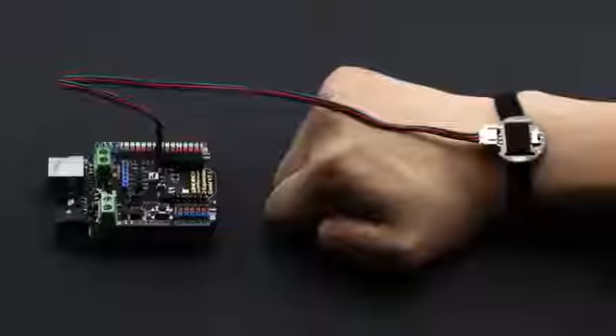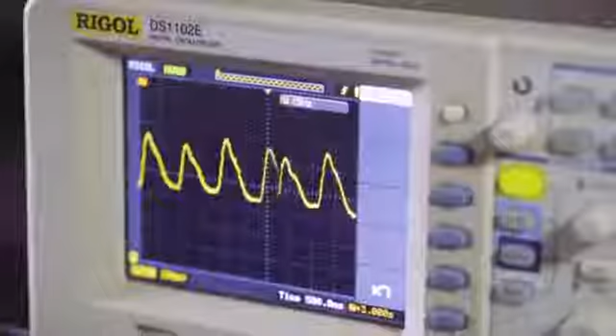Before moving into setup, let's first take a look at the optical heart rate sensor and how it works. The optical heart rate sensor is based on PPG, photoplethysmography technology, which may sound horrible to most of us. However, it is based on a very simple fact: blood absorbs green light. Each time our heart beats, it pumps a blood pulse into the vessel. As a result, more green light is absorbed. Therefore, the intensity of reflected light captured by the optical sensor gives us the density of the blood pulse.